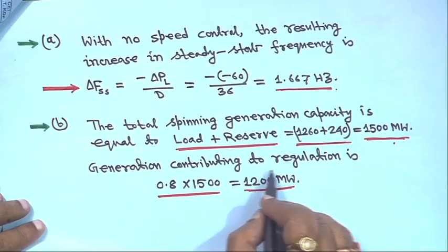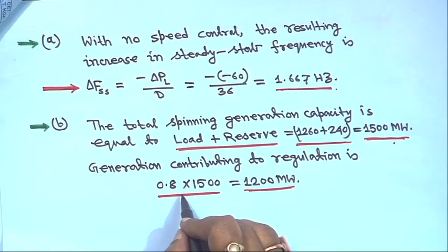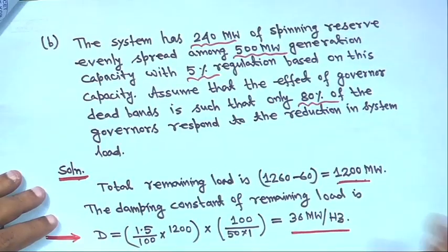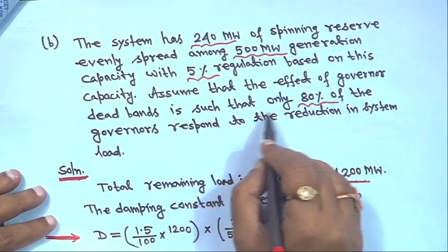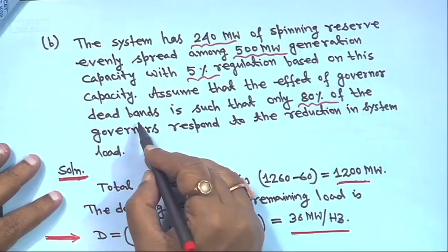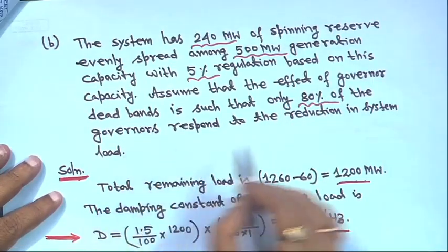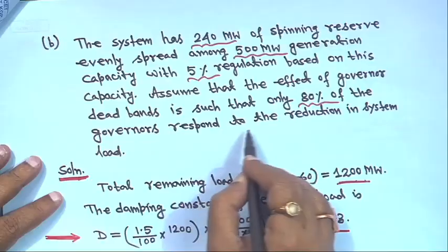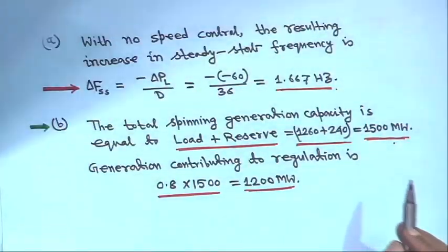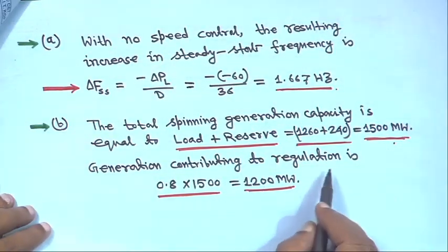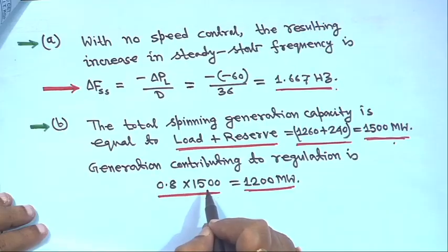Generation contributing to regulation: it is given that the governor deadband is such that only 80% of the governors respond to the reduction in system load. The deadband would not cover this in practice, but for numerical sake we have taken it. So generation contributing to regulation is 0.8 into 1500, so 1200 megawatt.